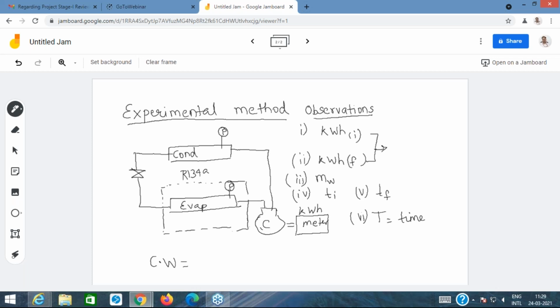So that is called the energy meter constant. So when you calibrate, the energy meter constant is fixed. Calibration means what? When you are actually measuring a known quantity of energy, 1 kWh, then you record the number of pulses for that 1 kWh.